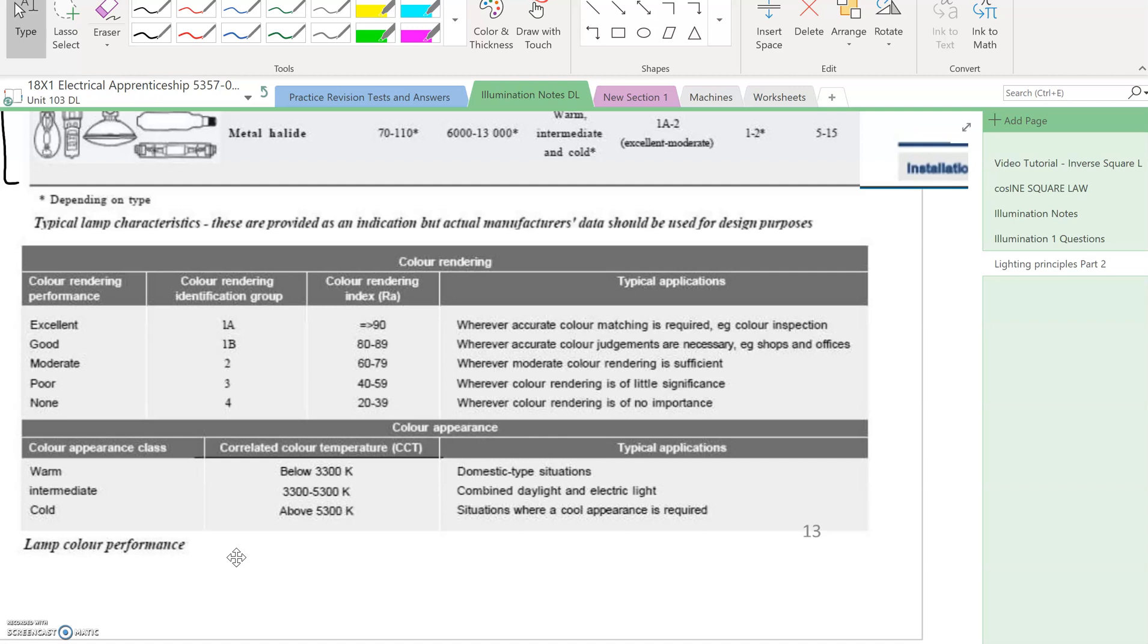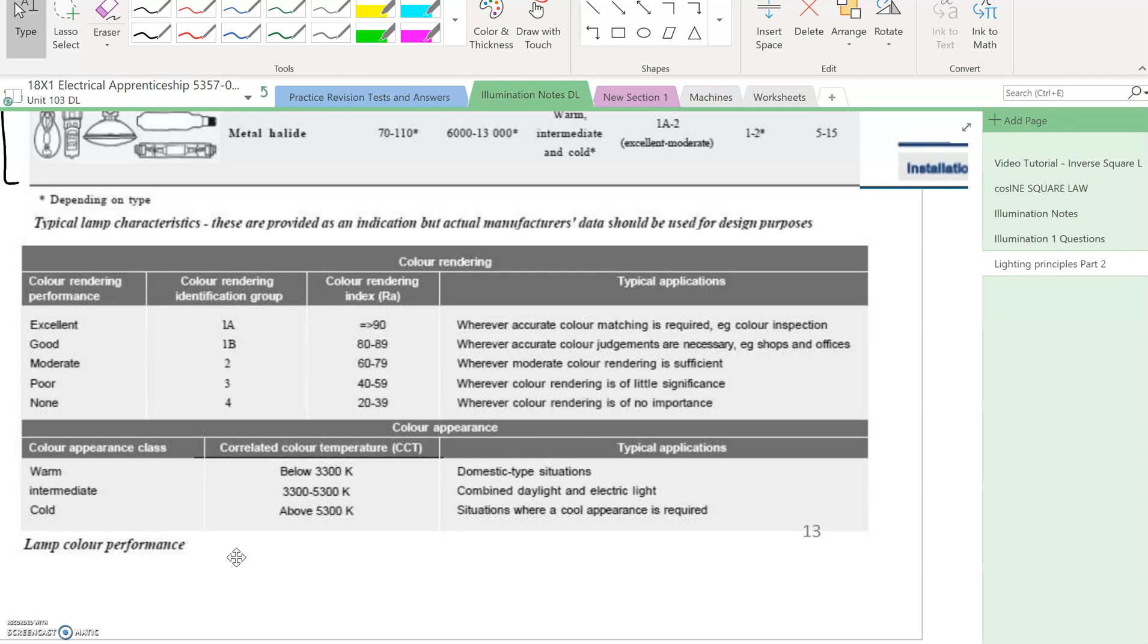Intermediate is 3300 to 5300 Kelvin, this information is from the CIBSE guide. Cold is above 5300 Kelvin, like clinical settings. You get cool white in situations requiring a cool appearance, like hospitals, dental practices, and food preparation areas with very clear white light.